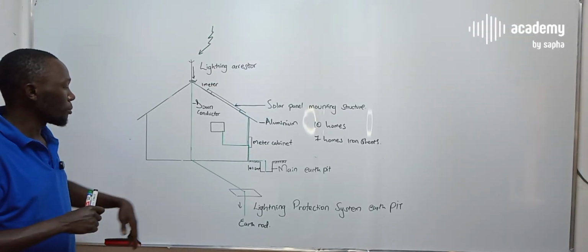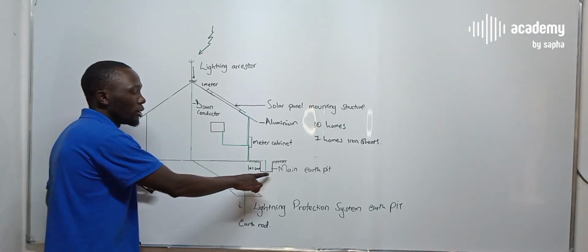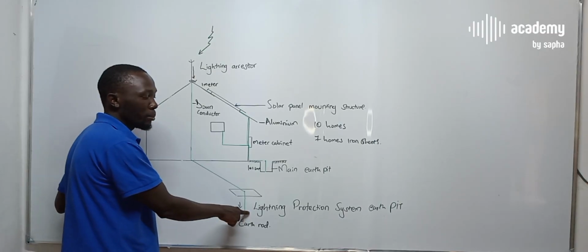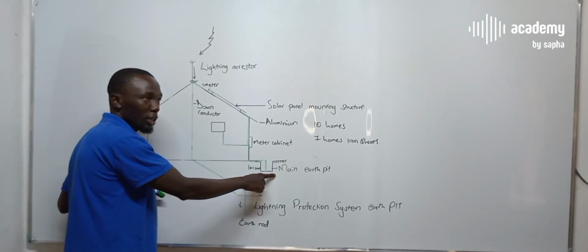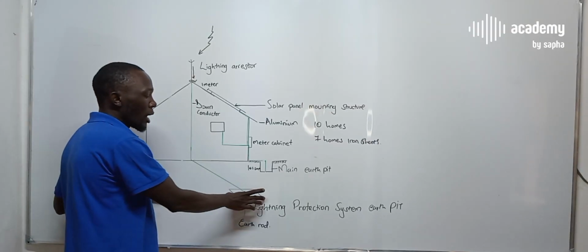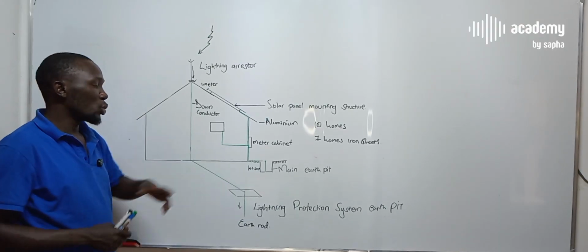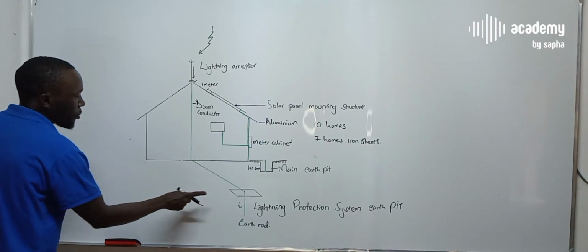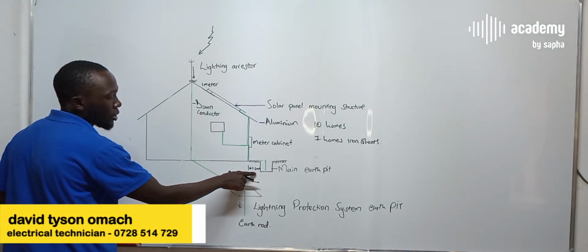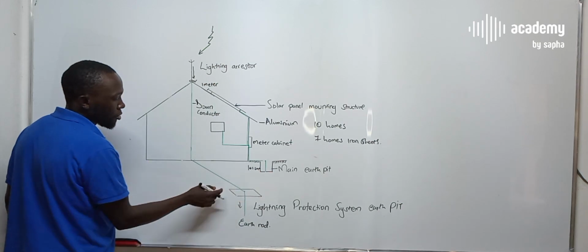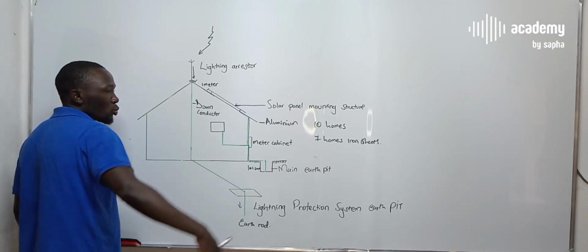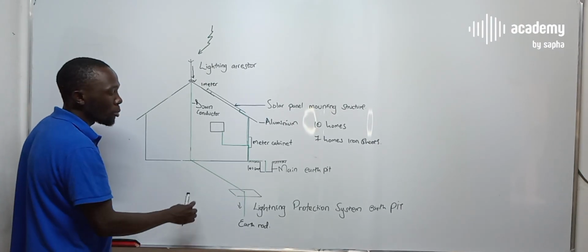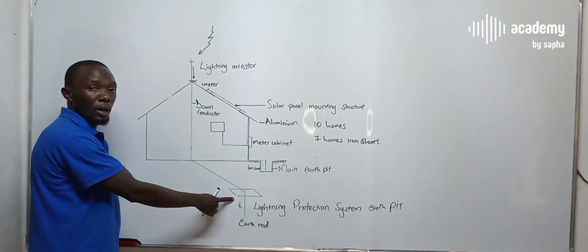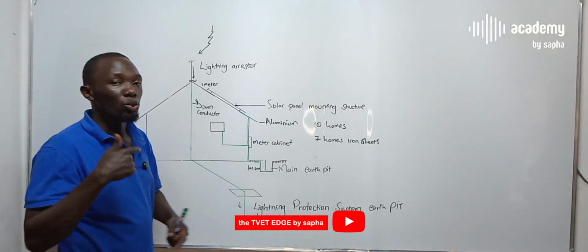Now, another thing you have to remember, this earth pit is supposed to be different from the main earth pit. The earth pit of the lightning protection system is supposed to be different from the main earth pit. And some regulations say that this earth pit should be at least, you see the zones, we have got zones. If you look closely, this one for the main earth pit, I said at least 1.5 meters away from the building. This one should be more than that. So if this one is at 1.5, you can go another 1 meter. That could be zone 1, and then on zone 2 now, probably at the second meter is where you now locate your earth pit from the lightning arrestor. So you also have to ensure that the distance is maintained.